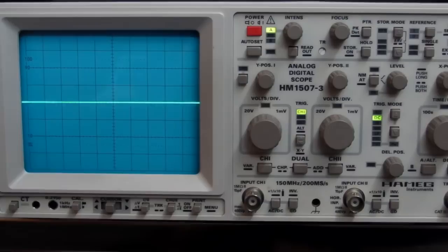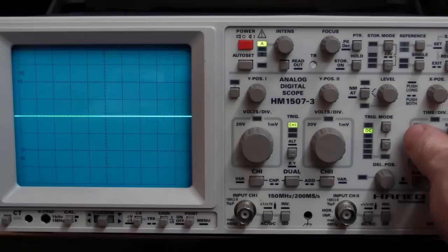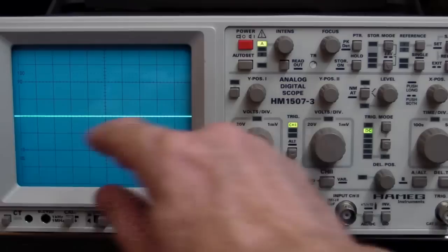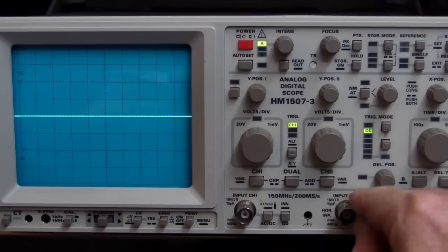Now, it's got a dedicated button, so you'd think it's a pretty darn important control, and it is. So let's take a look at the screen here when we operate the delay control. Now, if you remember that sweep waveform we had before, I've got it set to a very fast sweep speed, so you can't see it retrace or anything like that. Hold-off is off, or it's set to the minimum. Often they won't have an off, they'll just have minimum.